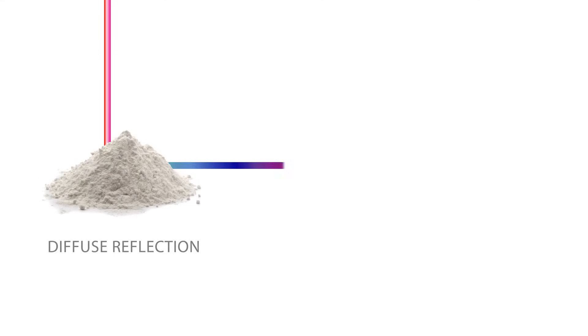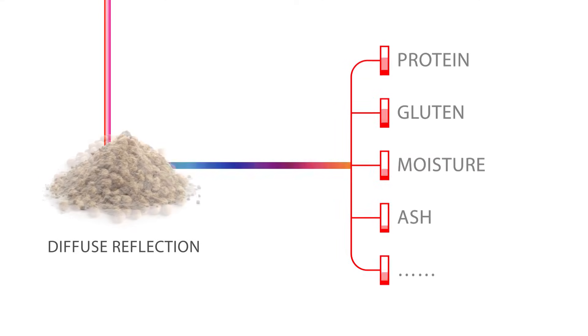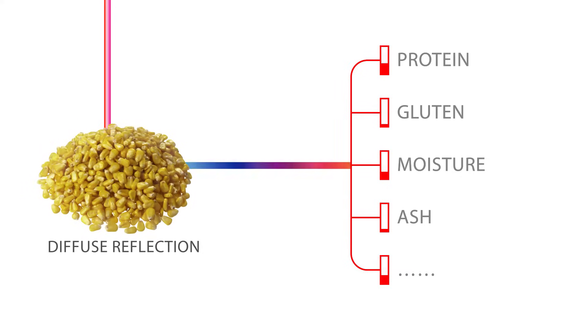The employed technology is Near-Infrared Diffuse Reflection Spectroscopy. The light reflected by the sample is analyzed and compared to a database in order to determine with precision the quantity of components found.